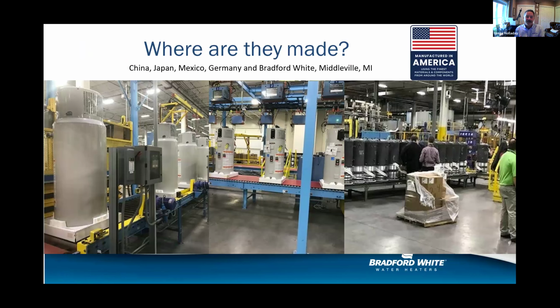It is an electric water heater that gets turned into an electric heat pump water heater, literally wrapping that condenser line on the outside of the tank, putting the casing around it in foam, filling that up, and adding the heat pump to the top.